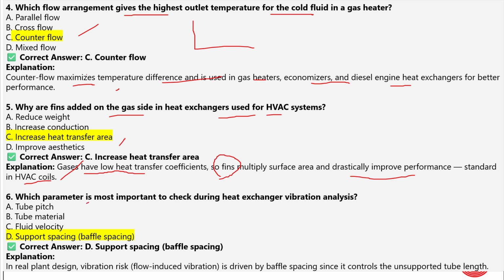Next question is, which parameter is most important to check during heat exchanger vibration analysis? So the answer is support spacing or baffle spacing. In a real plant design, vibration risk is driven by baffle spacing, since it controls the unsupported tube length. Baffles are provided so that the unsupported tube length can be supported. That's why it is a very important thing. Moving on to the next slide, guys.